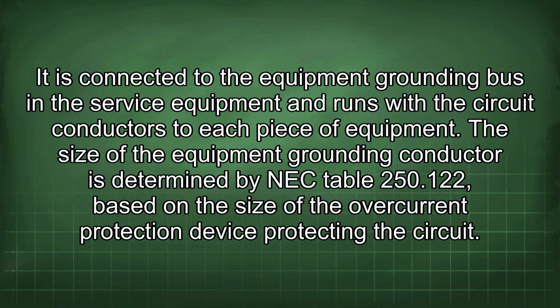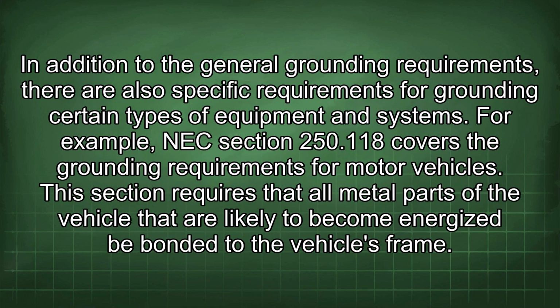The size of the equipment grounding conductor is determined by NEC Table 250.122 based on the size of the overcurrent protection device protecting the circuit. In addition to the general grounding requirements, there are also specific requirements for grounding certain types of equipment and systems.